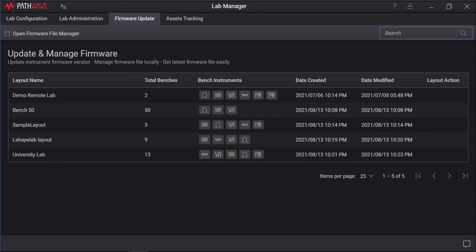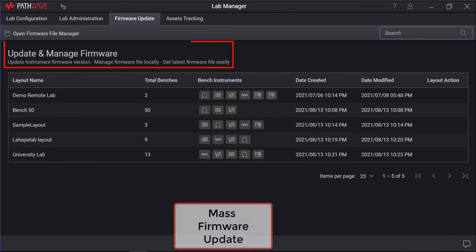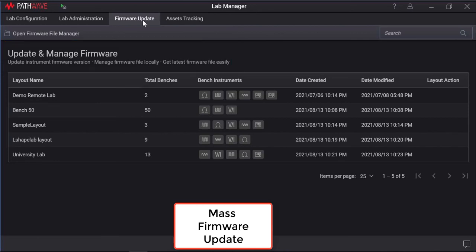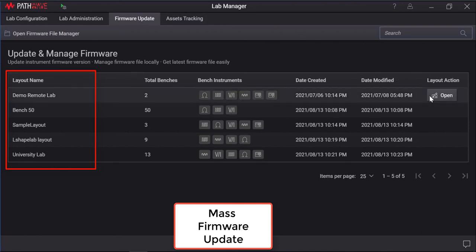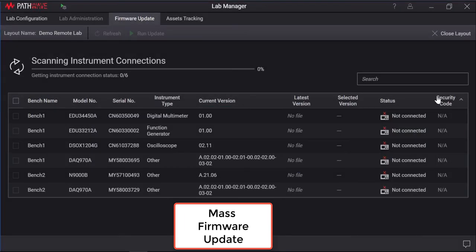The PathWave BenchVue Lab Manager includes a mass firmware update applications to update most of the Keysight instruments to the latest firmware available. Go to the firmware update tab. It will show a list of lab layouts. And select the lab layout for the instruments that you wish to perform a firmware update. Once the layout is selected, the application will scan all the connection details of the instruments.